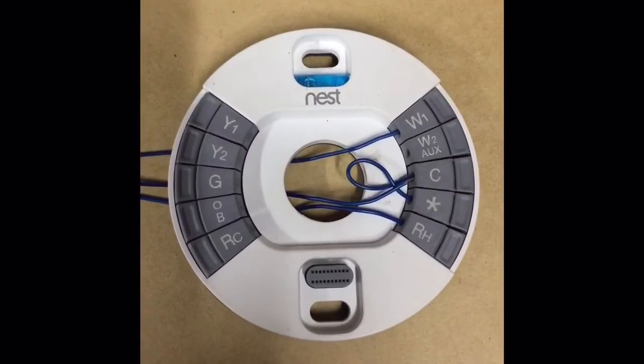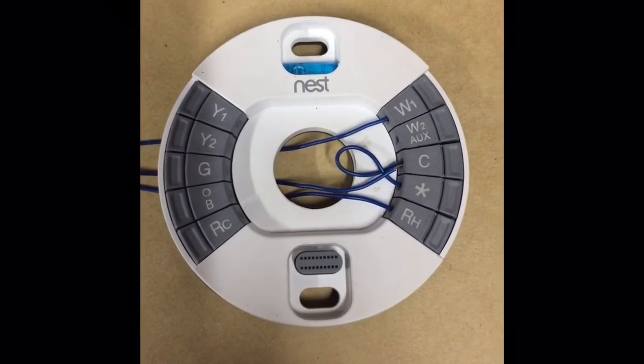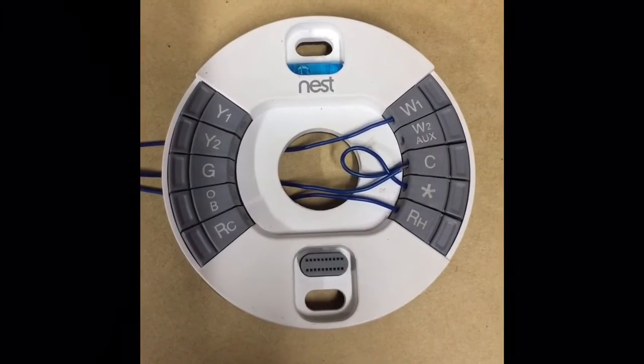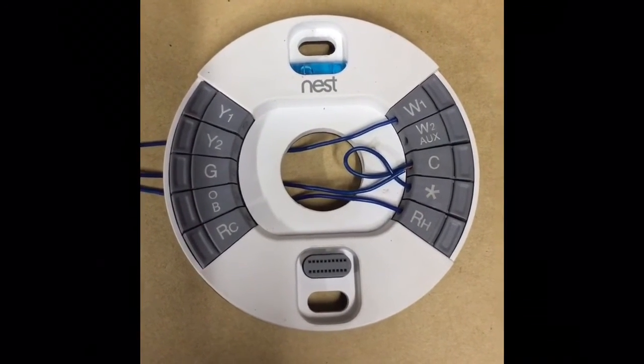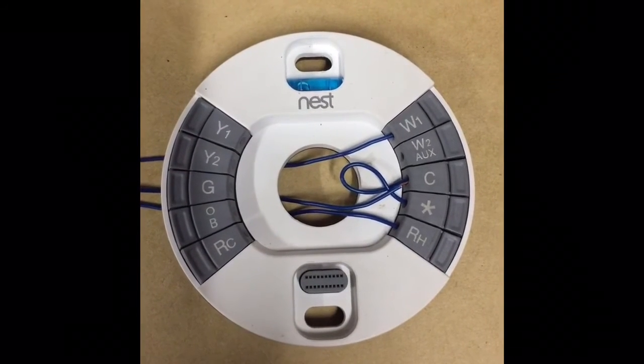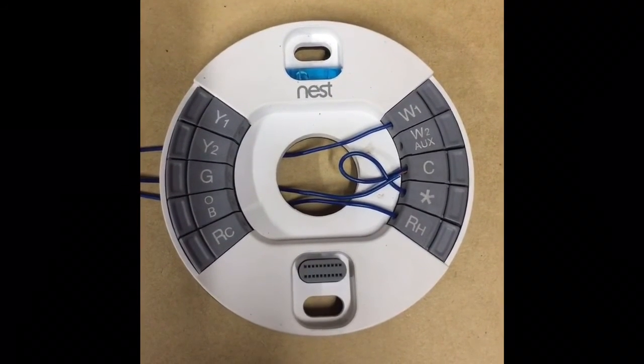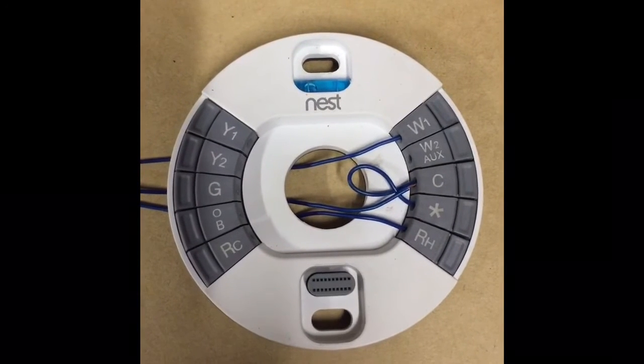So here we go, we've opened the box up and this is the base plate. The wires that we need are RH and W1. They're the existing wires on the wall. W1 is the switched wire, RH is the constant 24 volt. So we need to establish which one that is.